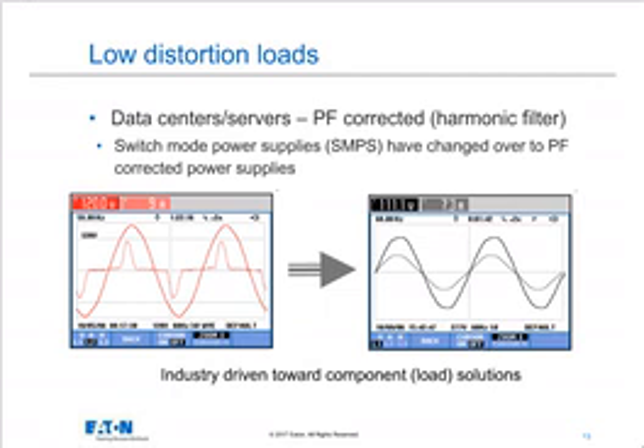With the loads themselves, what you'll see in data centers specifically is that the power factor corrected power supplies are now replacing what was the switch mode power supplies. So the switch mode power supply on the left had a significant amount of distortion. The one on the right, not much at all. In fact, it looks very much like a 60 hertz waveform.